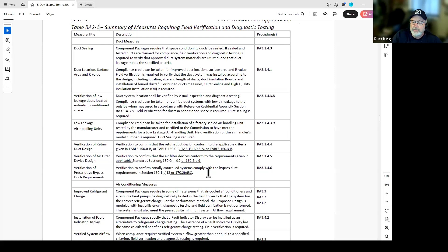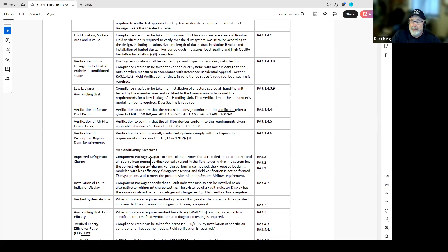If you're doing any kind of zonal control, the HERS rater has to go out. If they modeled it with a bypass duct, the HERS rater has to test it. Or if they model without a bypass duct, the HERS rater has to make sure that there's not one on there. Improve refrigerant charge. This is a big one. This one is very susceptible to weather. So if it's cold outside, you may not be able to do this test.